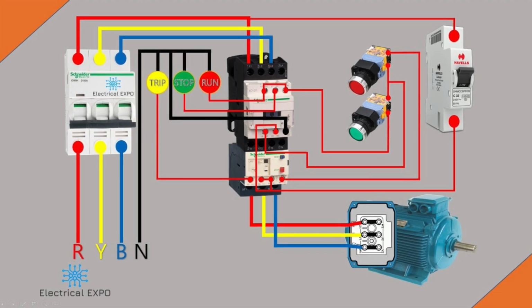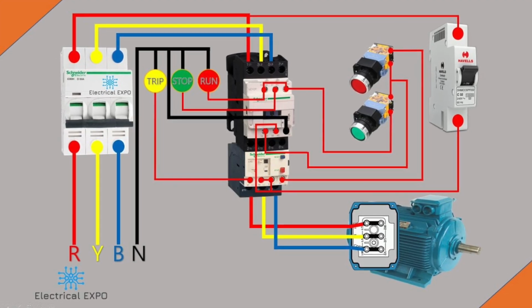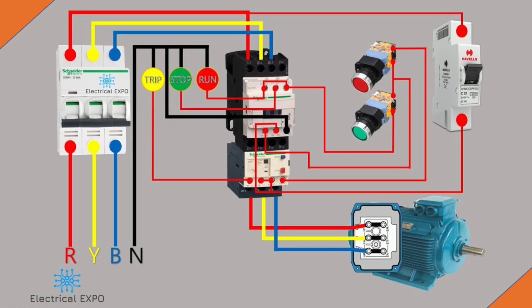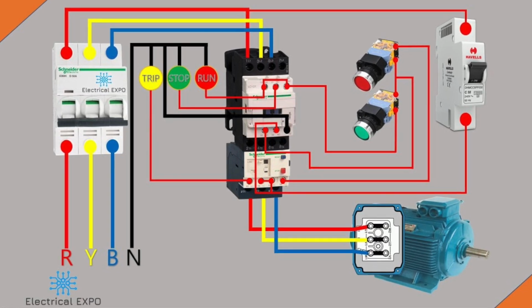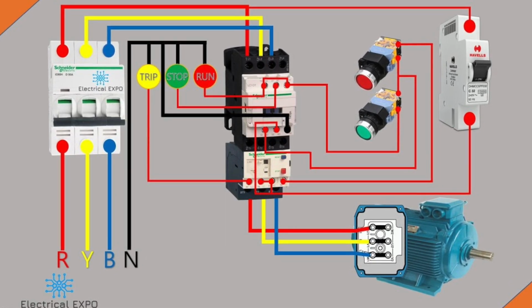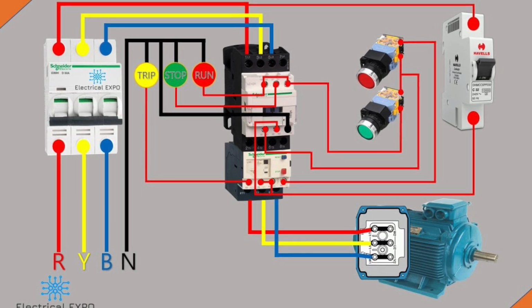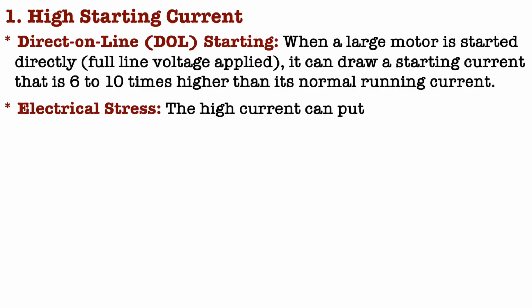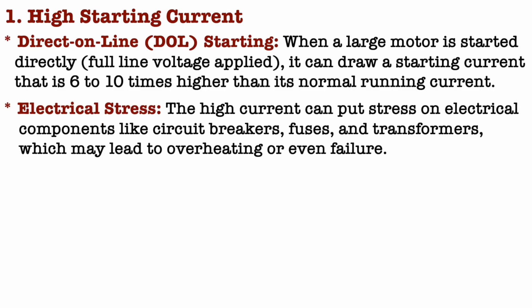This high inrush current can cause a significant voltage drop in power supply systems, potentially affecting other equipment connected to the same supply. Under this, next one is electrical stress. The high current can put stress on electrical components like circuit breakers, fuses, and transformers, which may lead to overheating or even failure. Second one is mechanical stress.